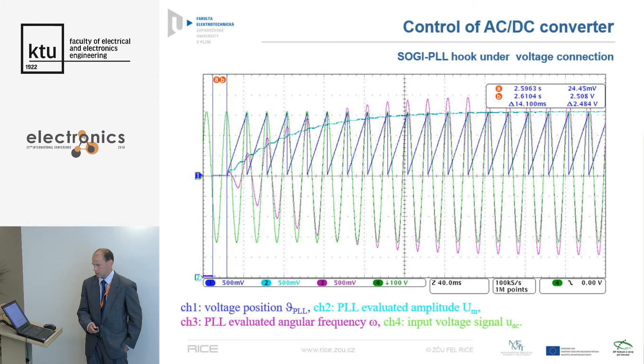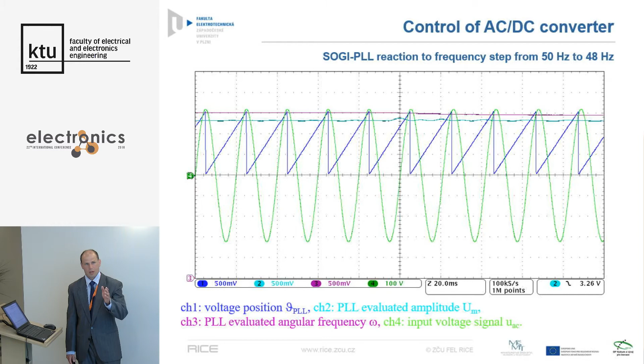The frequency of the trolley wire voltage is not constant. There is some fluctuation, approximately from 48 to 52 Hz. It's possible. And we tested our synchronization for step change from 50 to 48 Hz.